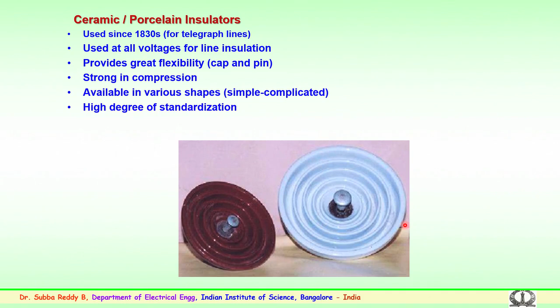Electrically they are fairly stable over time, almost a century. Mechanically they are subject to deterioration over time, and some issues were also noticed in ceramic or porcelain insulators over a period of time. These could be flashovers because of the surface getting degraded, or punctures, which could be because of cap and pin failures. The cement growth, as mentioned, is due to the expansion because of hydration, which causes radial cracks or punctures in the head, which have been noticed in the utilities.